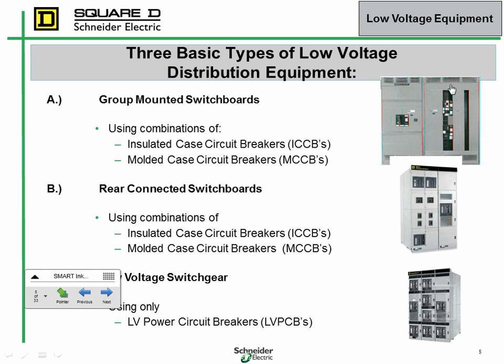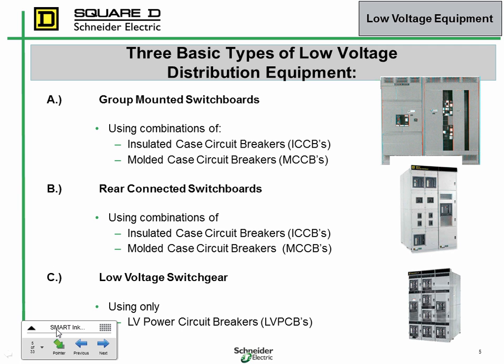Yeah. Okay, so anyway, switchgear, ANSI rated. The big difference is all the different compartments are isolated from one another. I've got some more pictures that show it, but the reason it's deep is because the front part of this gear is the breaker compartment. That's where the circuit breakers are mounted. Separated behind that is the bus compartments, and then separated behind that is the cable compartments where all the terminations are made.